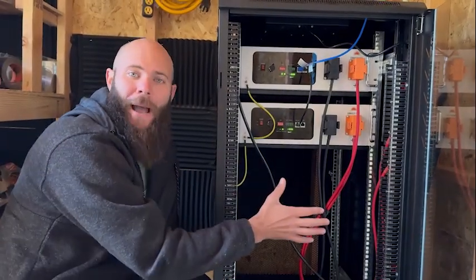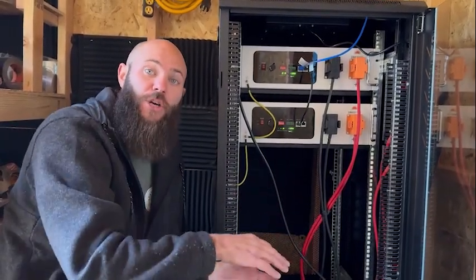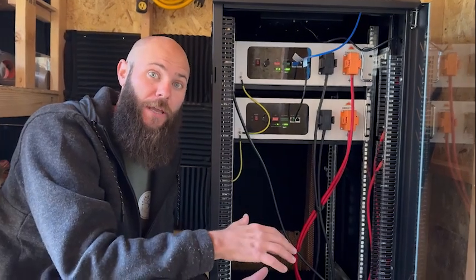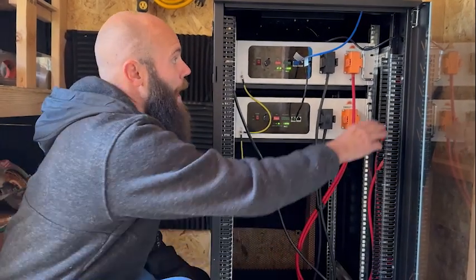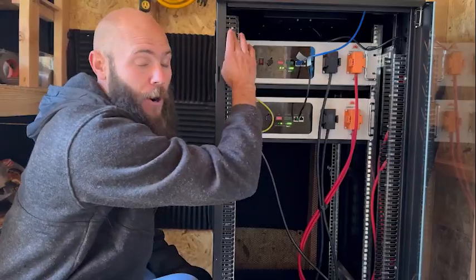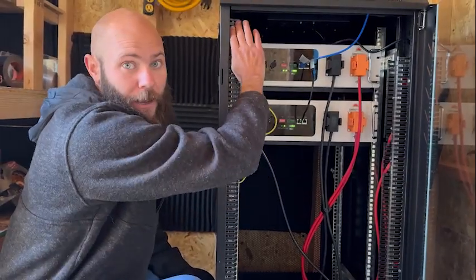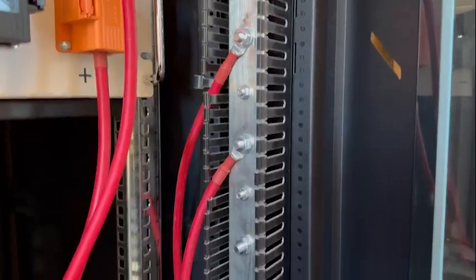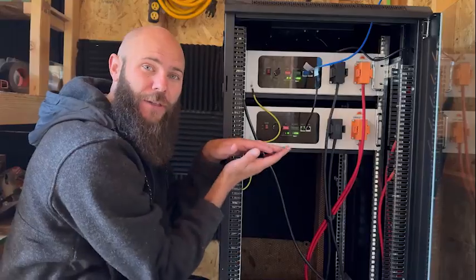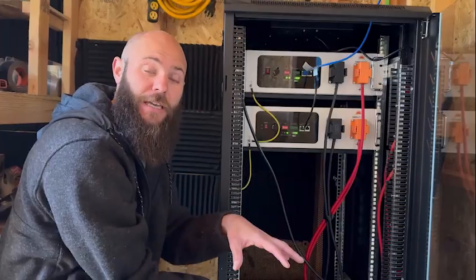To help my batteries in this parallel system charge and discharge a little more equally, rather than just pulling power from the top of my bus bars, I've got my negative main coming from here and my positive main coming from down here. That creates a cross-flow system so that each battery discharges and charges equally.